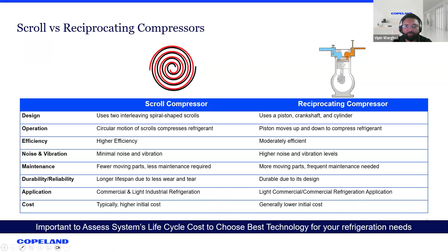So for a small application, wherein the reciprocating compressor would have a lower initial cost, the cost may play quite an important role, so maybe reciprocating compression technology is better for your requirement. While in light industrial refrigeration, such as a cold room which has a high level of variation in cooling load, I think scroll could be a proper choice for that kind of application. So this is how these two technologies are compared with each other.